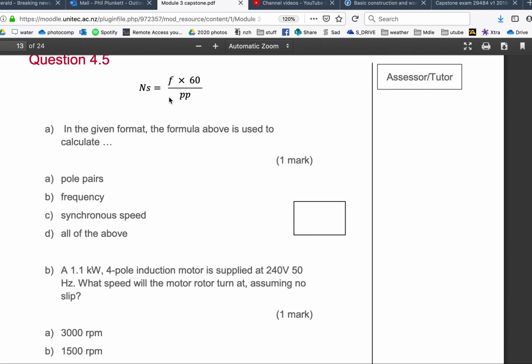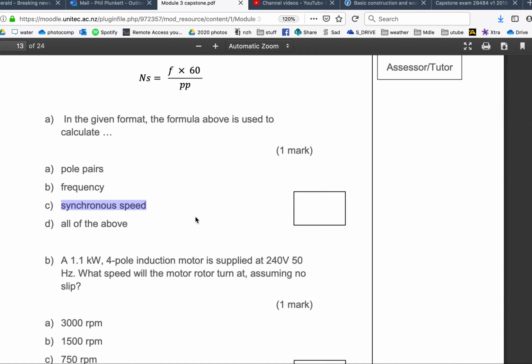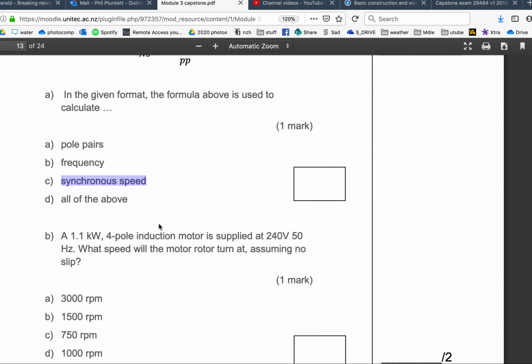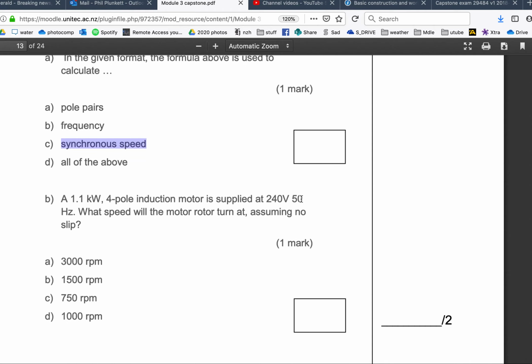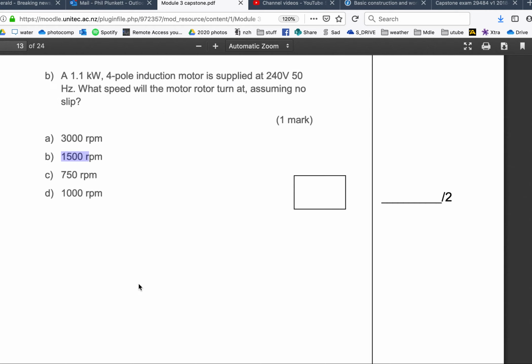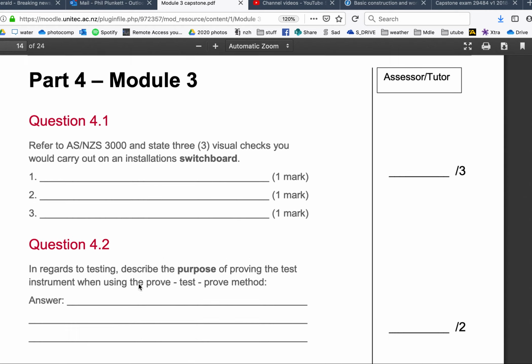Here's our speed. What's this given? It's to give the synchronous speed. In the given format, NS is synchronous speed. So you can do that. 50 times 60 is 3000. 4 pole, so that's 2 pairs. 3000 divided by 2, 1500. Done heaps of those.